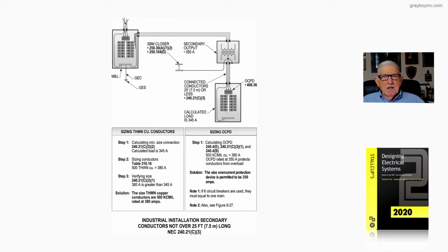Step 2, 310.16, to supply 345, it takes a 500 kcmil in the 75-degree column in table 310.16, which is 380 amps for that conductor, and it will supply 345. The overcurrent protection device, we will select it next, but right now we're just selecting in this boxed-in information, sizing THWN copper conductors, we're selecting a 500 kcmil THWN copper conductor at 380 amps to supply 345 amps in step 1, and that's what the solution is giving us.